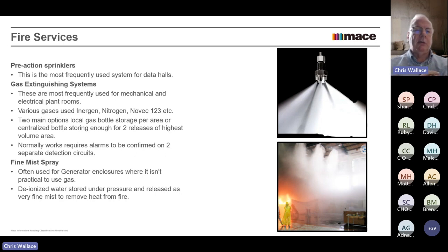Most of the data centers used to have extinguishing systems. They're not as much having extinguishing systems now. They normally just reserve them for the switch rooms. Different sorts of gases you can use. And again, you can either have a local bottle store per area or a centralized bottle store. Quite often we're finding that people have a centralized bottle store and they look at the worst case discharge and have allowed for two worst case discharges through the whole building, against a double knock system.